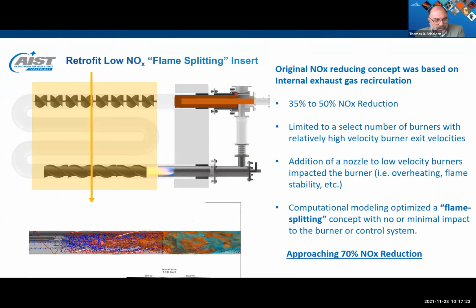Initially, internal exhaust gas recirculation was explored as an effective means of reducing NOx. While a reduction in the range of 35 to 50% was achieved, it was limited to a few burners or required modifications to existing burners. Here is a visual demonstration of the concept. So here we have a nozzle, combustion occurring inside the device, and then recirculating the exhaust gas to help reduce NOx.